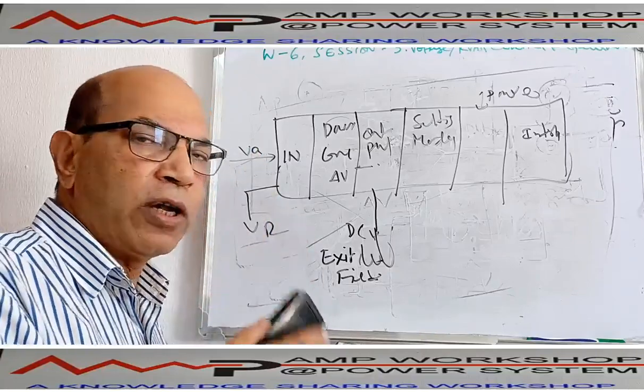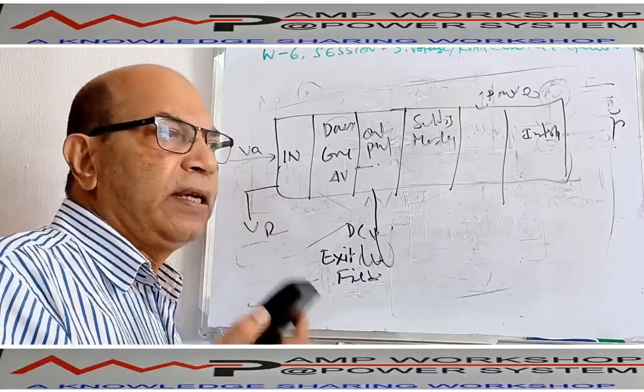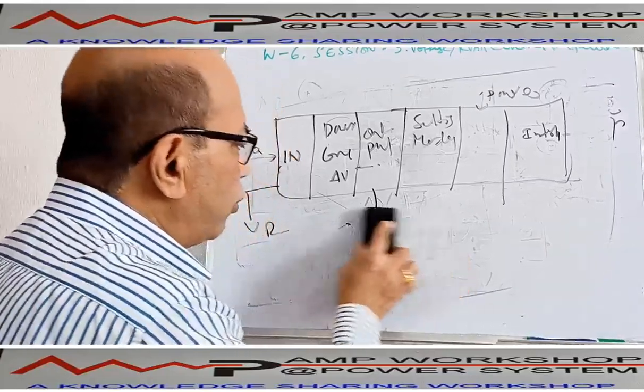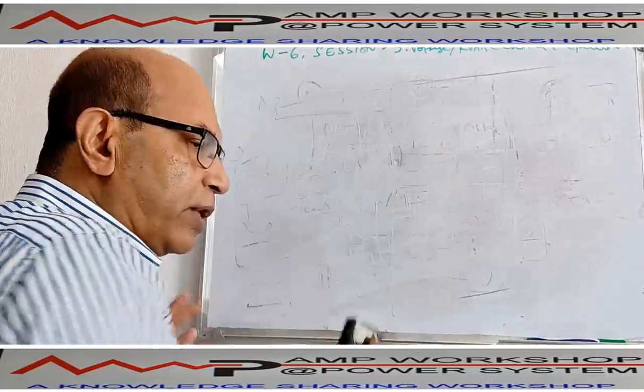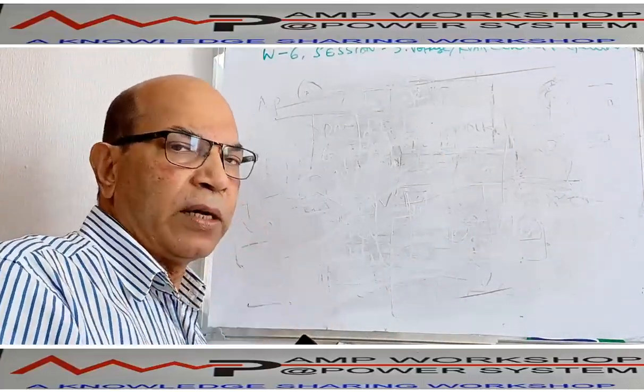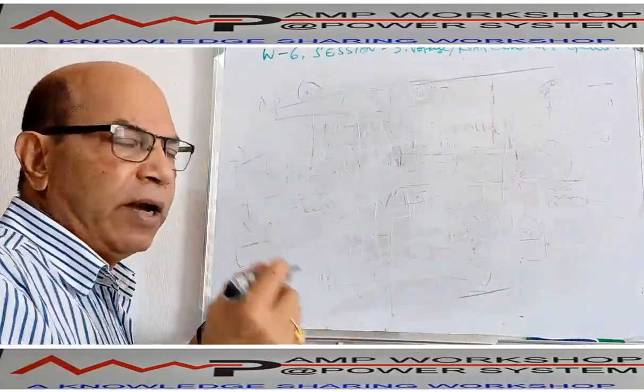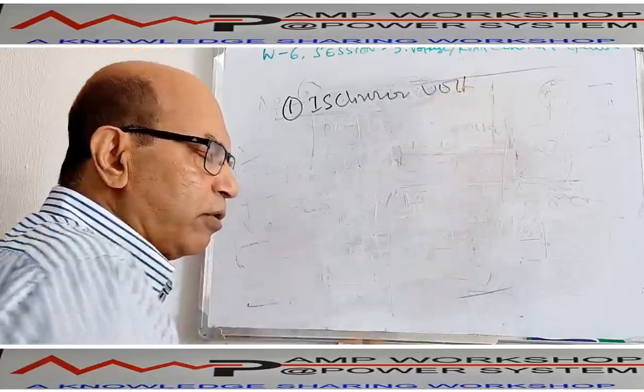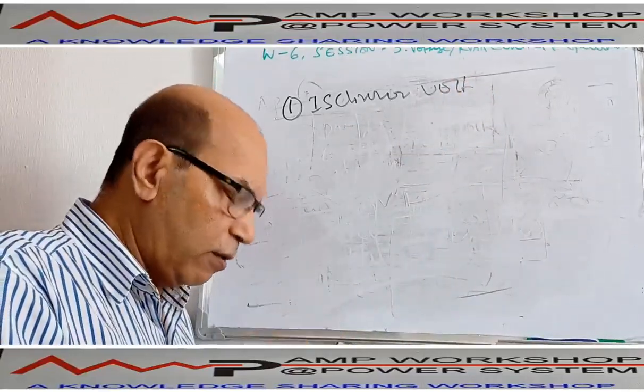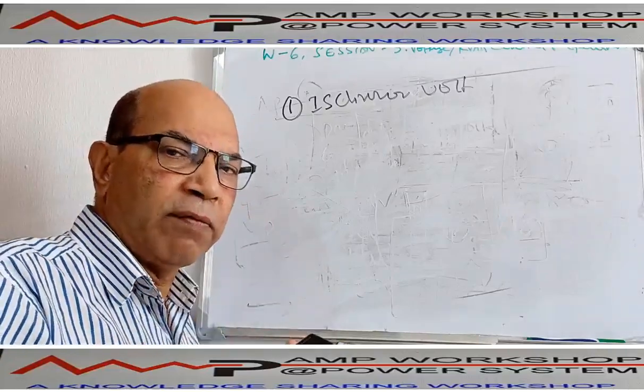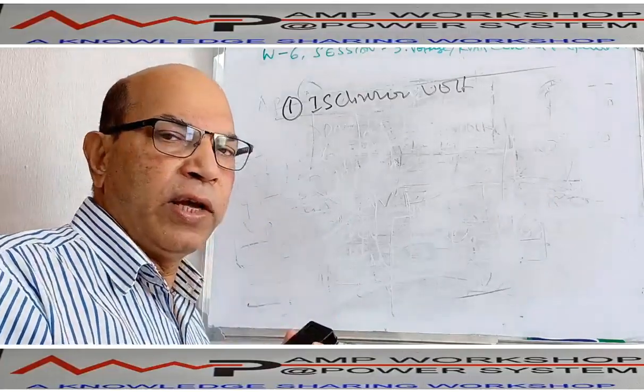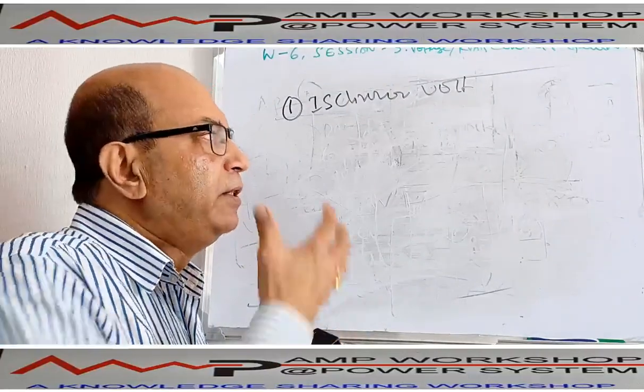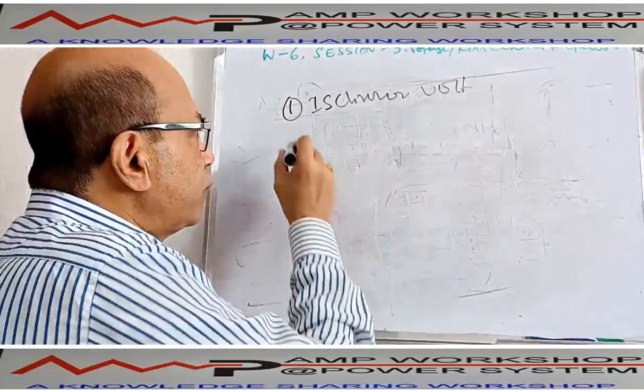Here, the voltage controller also works in the same way. It has two modes. One is called isochronous mode. In isochronous mode, this voltage controller works in such a way that you cannot change the voltage of the generator. Generator voltage will be maintained constant, whatever the reactive power you withdraw from the generator. That is called isochronous voltage control mode. This voltage control device works in two modes. One mode we call isochronous voltage mode. In the isochronous voltage mode, same like the isochronous speed controller, the voltage at the generator output terminal will be maintained constant despite changing reactive power. Either you increase the reactive power drawing or you reduce it, generator terminal voltage will be maintained constant. In that case, we call it isochronous voltage mode.